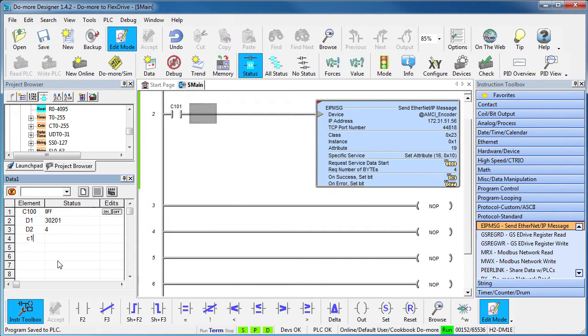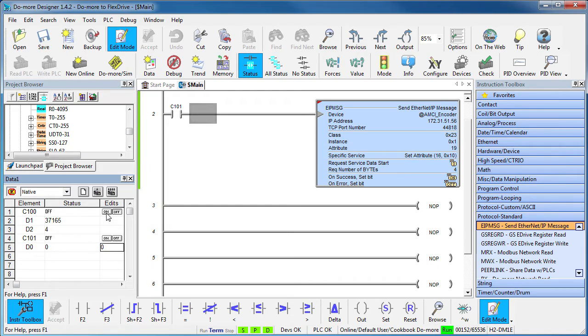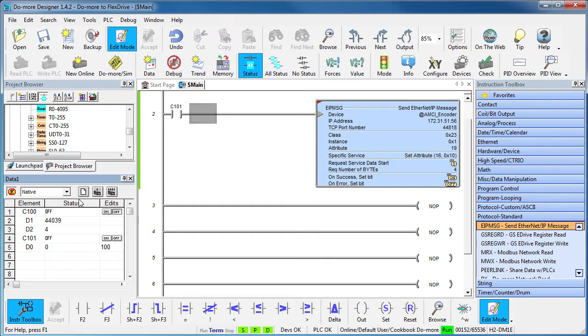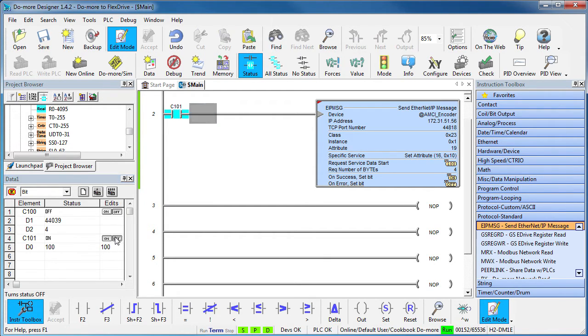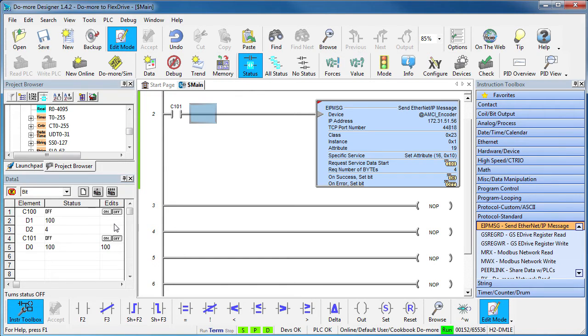Let's add our preset to the data view along with its control bit. Make sure we are running, rotate the encoder a little and read the current value of the encoder. Now let's set our preset at 100 and toggle its control bit to write it to the encoder. Now toggle the encoder value bit and it's right where we expect it to be. And that's all there is to talking to an encoder – any Ethernet IP enabled encoder from the do more.